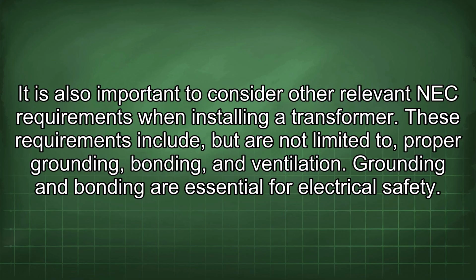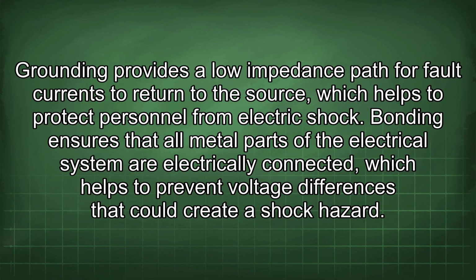It is also important to consider other relevant NEC requirements when installing a transformer. These requirements include, but are not limited to, proper grounding, bonding, and ventilation. Grounding and bonding are essential for electrical safety. Grounding provides a low impedance path for fault currents to return to the source, which helps to protect personnel from electric shock. Bonding ensures that all metal parts of the electrical system are electrically connected, which helps to prevent voltage differences that could create a shock hazard.